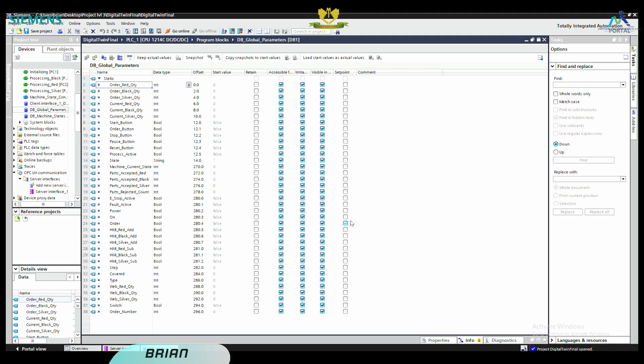On the software side, a Python client using an OPC-UA library connects to the PLC's endpoint over TCP. So once it is connected, it can read any node, such as machine state, accepted part counts, rejected part counts, and write to nodes like quantity set points and button triggers. Writing a Boolean true to a button node replicates the physical rising edge exactly as the PLC ladder logic expects.